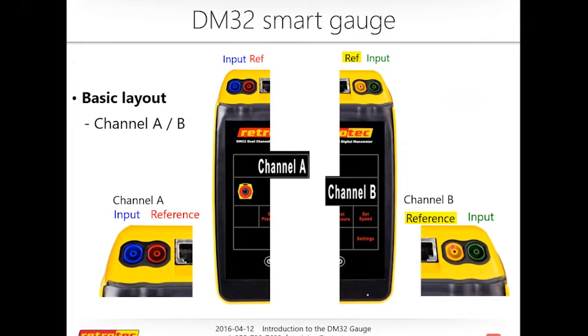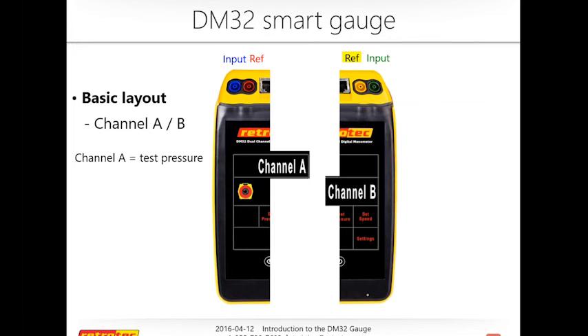So let's take a look at how those work. Channel A is normally considered pressure or test pressure. Now with channel A, you can make your choice of pressures. You can use inches of water column. You can use Pascal. You can choose even, I think, pounds per square foot, depending on what you test at. But that's usually the test pressure.